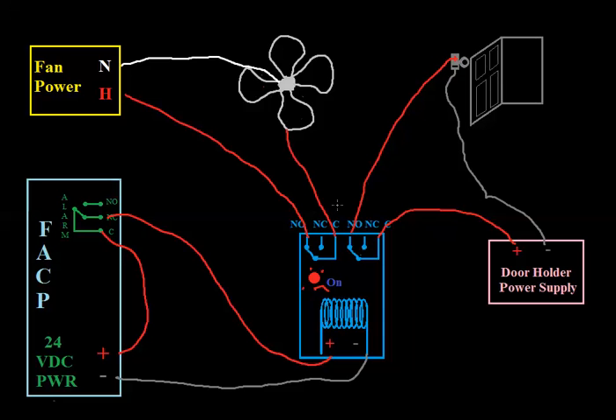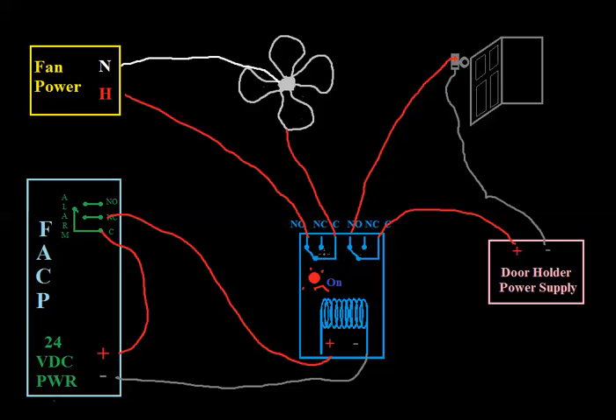There are a lot of lines going across the screen, but it's all pretty simple if you look at it one at a time. The alarm circuit is complete coming off the panel — we took 24 volts through common and normally closed, so there are no opens. If I were to cut one of these wires, all these relays would change states, your fans would shut down, and your doors would close. Similarly, if the panel goes into alarm, this relay is going to open up, you'll lose power on your relay, and you'll open up both the fan circuit and the door holder circuit — fans shut down, doors close. You could make as many chains of relays as you want using a relay like this, since they even make relays with four individual outputs.